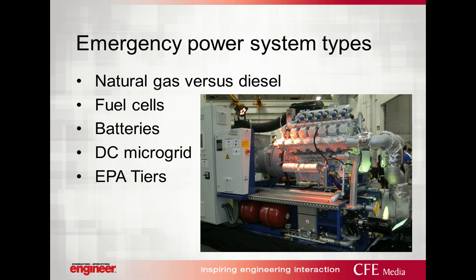The issue with natural gas is the lack of on-site storage. A letter from the gas company stating the reliability of their system might be sufficient for an AHJ to approve the use of natural gas. Designers will refer back to my previous discussion on risk assessment, and they can apply that logic to their specific project, regardless of building occupancy. If the failure of a natural gas supply only results in the inconvenience or discomfort of the occupants, then using natural gas for a generator could be an excellent option.